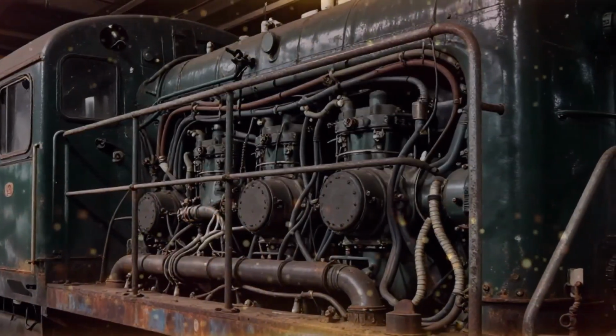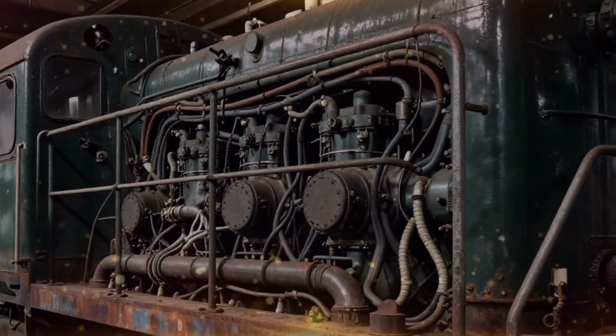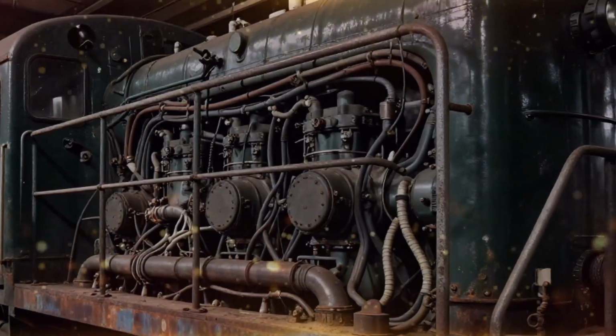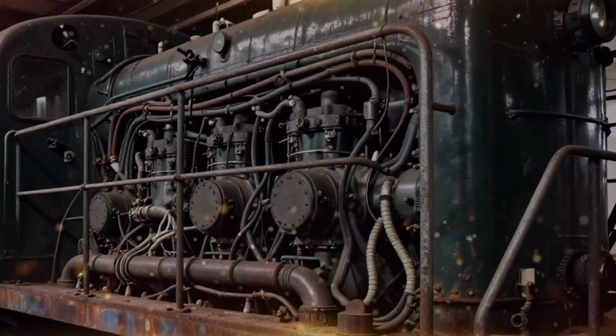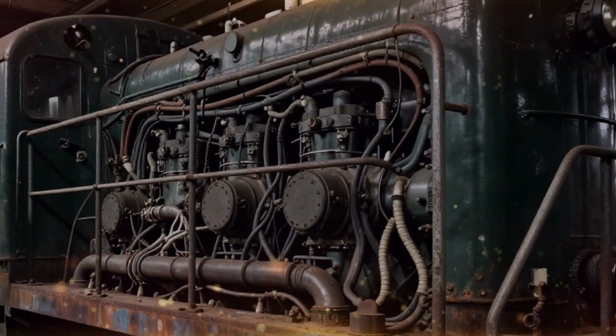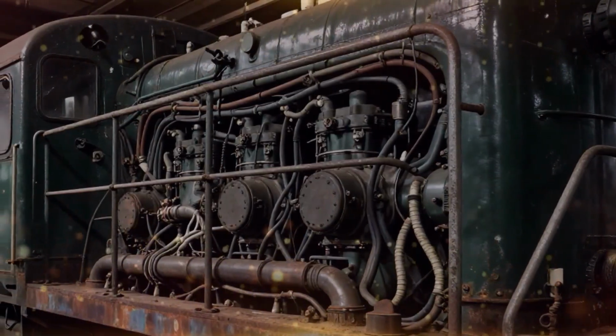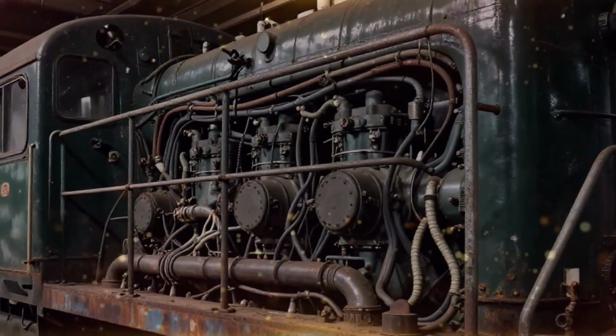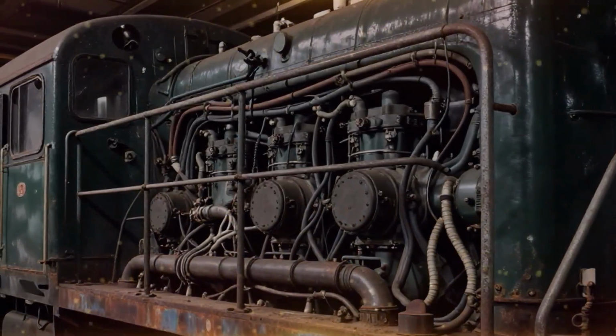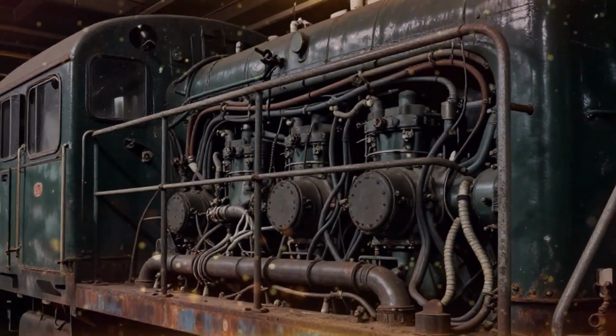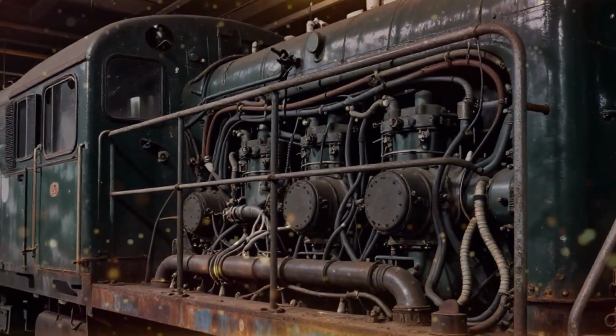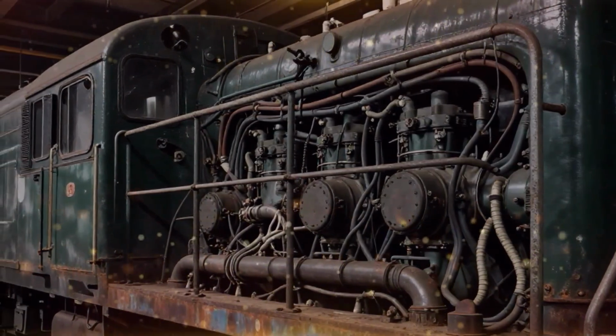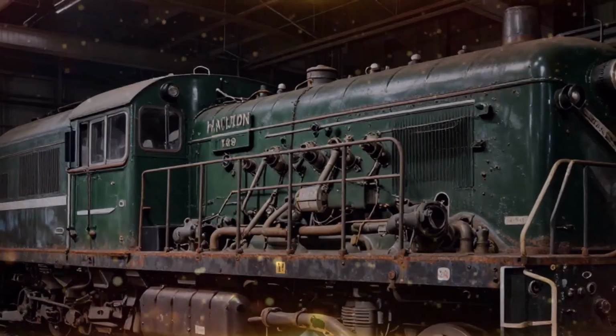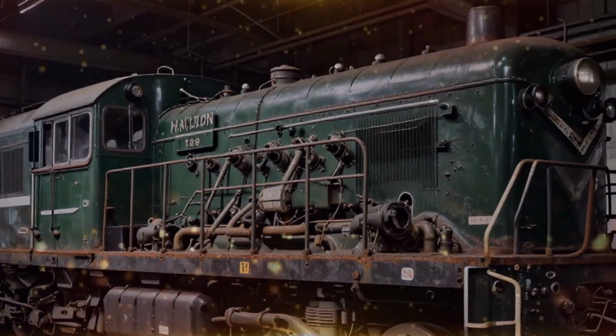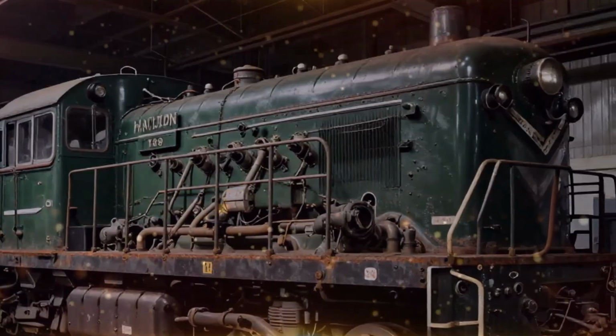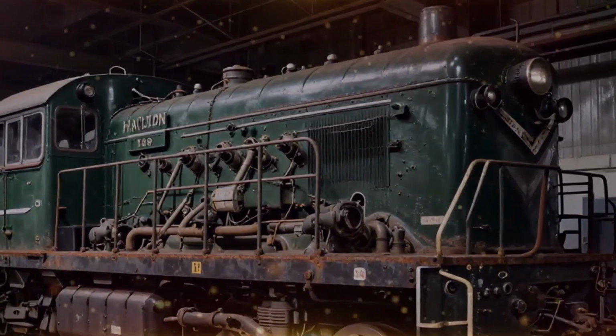When you approach a machine like this, you have to abandon the mindset of a parts changer. You cannot simply order a replacement module from a catalog. You have to become a specialist in industrial archaeology. You have to look for the mechanical truth hidden in the wear patterns of the metal. The specialist doesn't look for a screen. They look for the physical evidence of operation. They trace the hydraulic lines of the governor, feeling for the viscosity of the oil. They inspect the silver contacts on the relays for the telltale pitting of electrical arcing. They understand that the machine is a closed system of pressure and resistance.